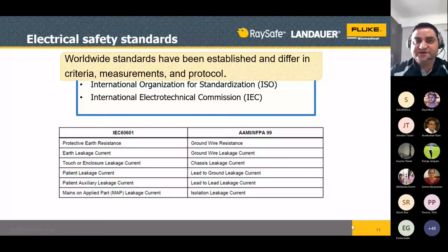Worldwide standards have been established and differ in criteria, measurement and protocols. We have the International Organization for Standardization, ISO, and IEC; we are talking about IEC today. For electrical safety we have to do a lot of tests, but these are the tests of most importance. Protective earth resistance we can measure. Earth leakage currents, as I said, touch and enclosure leakage current. If you touch any instrument, it should not give any kind of shock to you. For that, this standard is there. You can check whether it is within the permissible limit or not. If it is not, then please report it and get the equipment repaired. And after you repair the instrument, you have to do the test again. That is the protocol.